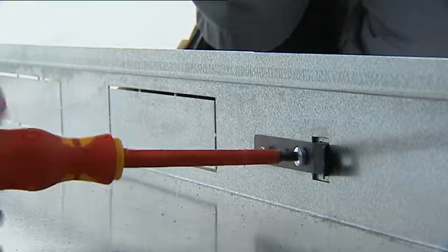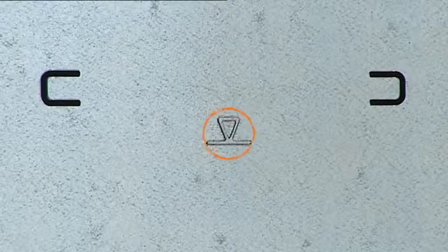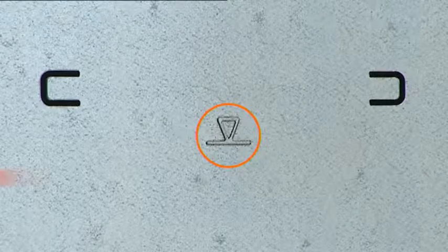In order to ensure maximum safety, the holding springs must be secured with the appropriate screws. The symbol on the flush mounting back marks the 1 m level, and it is imperative that it is aligned with the 1 m height mark on the site wall.